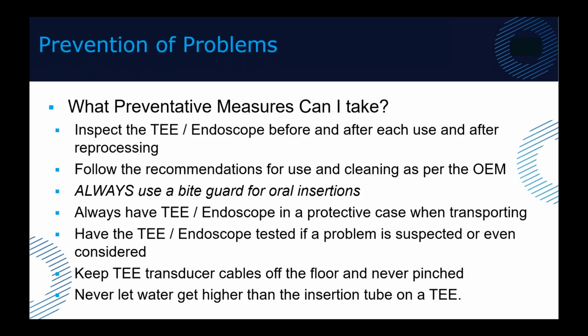When it comes to ultrasound cables, the cable that comes out of the connector, keep those off the floor. Cables on the floor tend to get stepped on, they tend to get pulled, you can actually rip one out of a machine, those kind of things can happen. And never let water get higher than the insertion tube on a TEE.